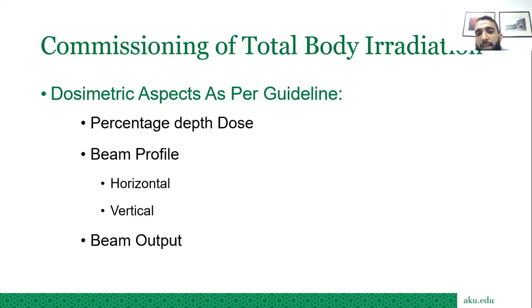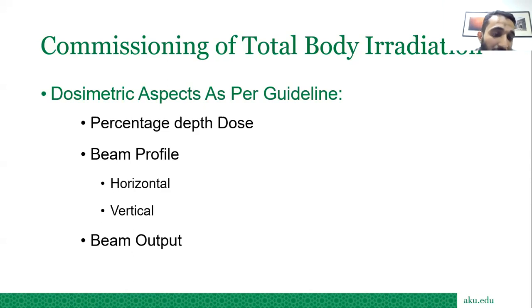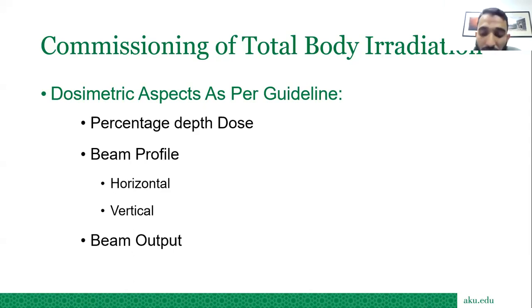For the dosimetric aspect per guideline, we need three types of beam data to commission TBI: percentage depth dose (PDD), which shows how dose changes as the beam penetrates the patient; beam profile, showing how the beam shape changes at extended SSD; and beam output at the extended SSD. We measured both horizontal and vertical profiles, and beam output at extended SSD.